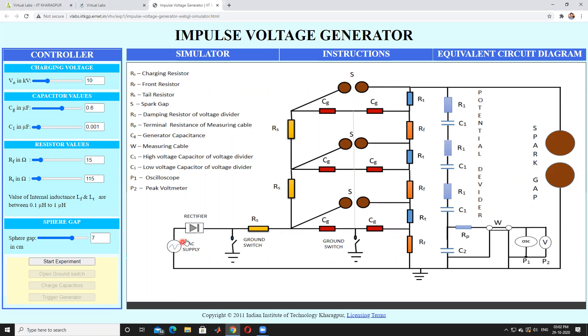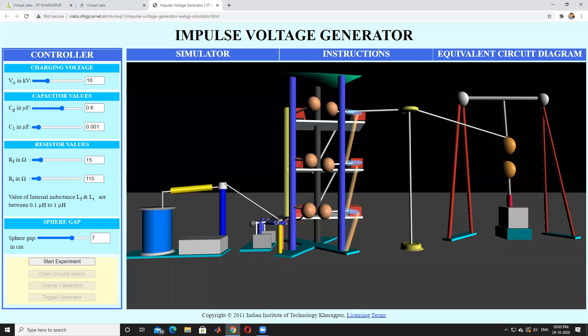This is the supply voltage. By using a rectifier, we convert AC to DC, and then all the capacitors are charged. During the starting condition, the spark gap - we have to maintain some distance between the two electrodes. Under this open condition, all capacitors are charging in parallel. RS is called the charging resistor, RF is called the front resistor, and RT is called the tail resistor. By using RF and RT, we control the wave front time and wave tail time respectively.